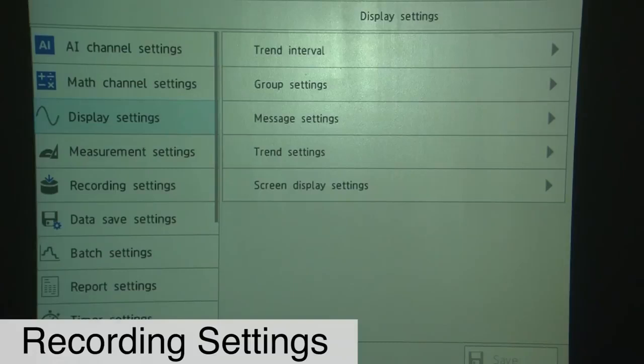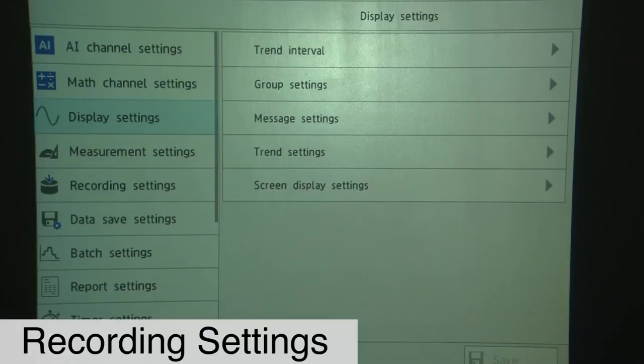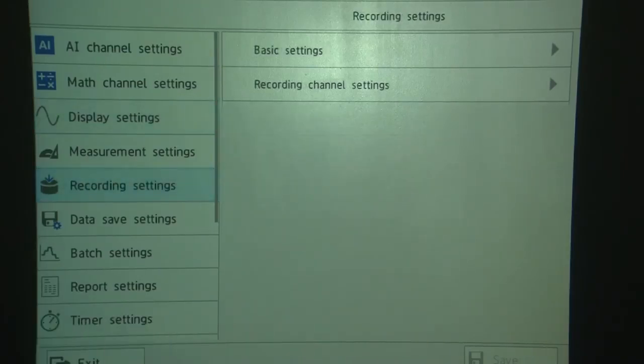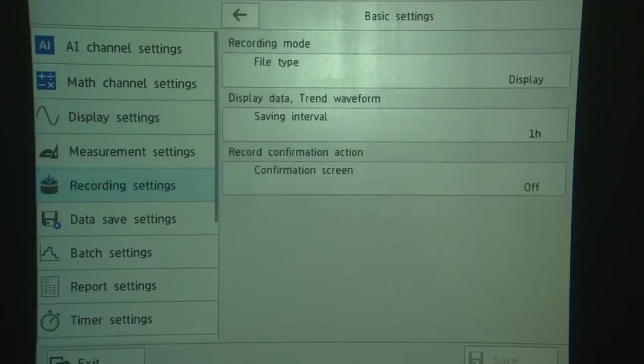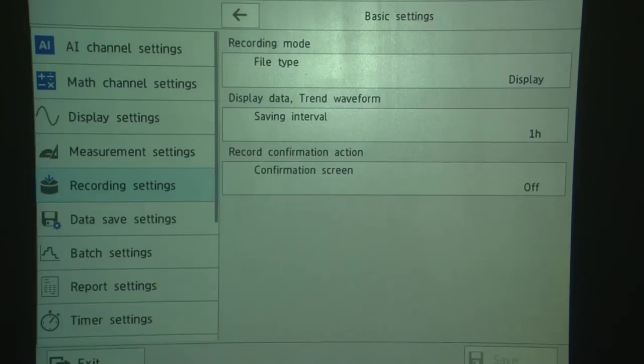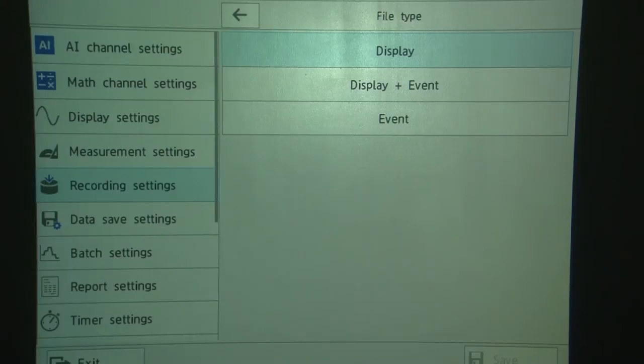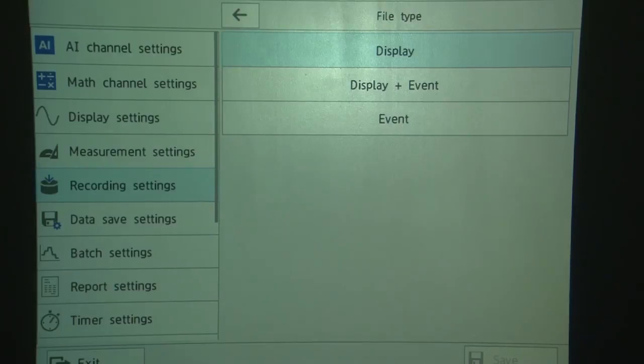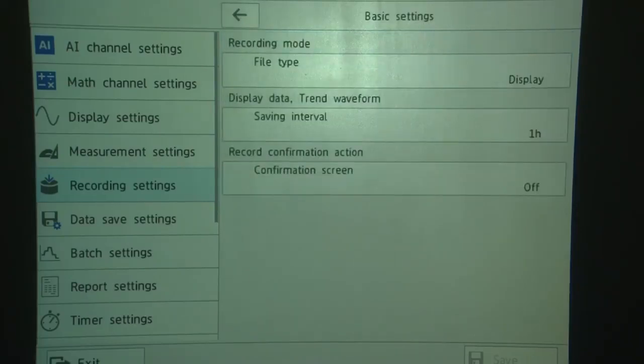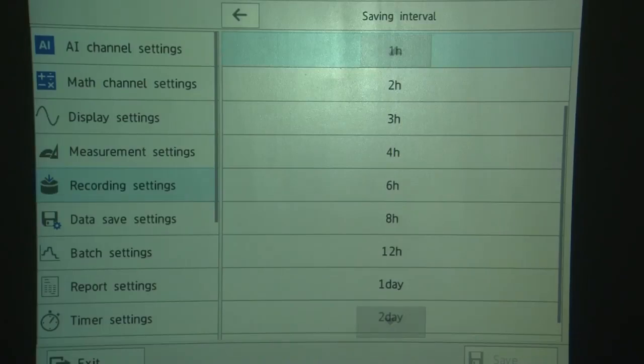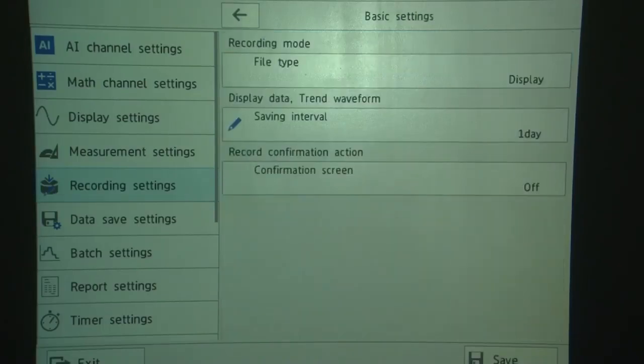First thing we're going to do is touch Recording Settings. We're going to go to Basic Settings. We're going to make sure Display File Type is chosen. When you touch the menu, you'll see a choice, Display and Event File, or Event File Only. And the Display Data File is a file type that records the Trend Data, which is min, max channel values that are stored at the Trend Update. An Event File is simply instantaneous channel data recorded at a fixed interval. So we're going to use Display Data. And we're done on this screen, so we're going to hit the back arrow. We're going to go to the Saving Interval. And we're going to select one day for the interval, which is 24 hours. And we're going to touch Save.